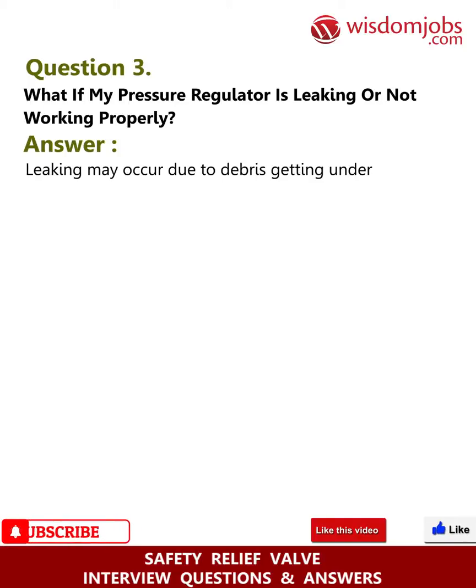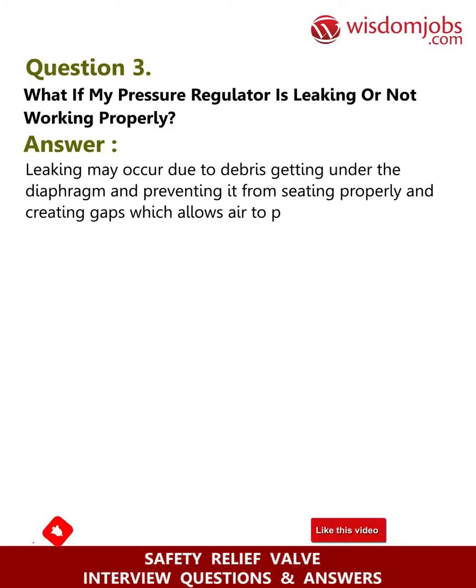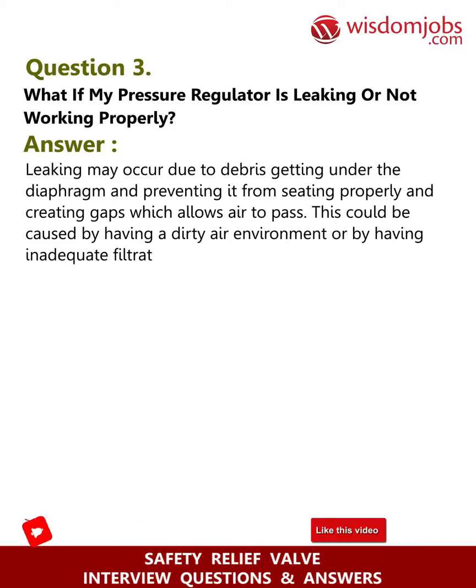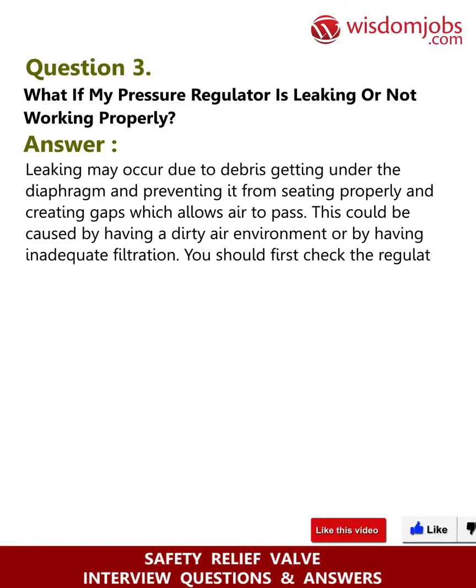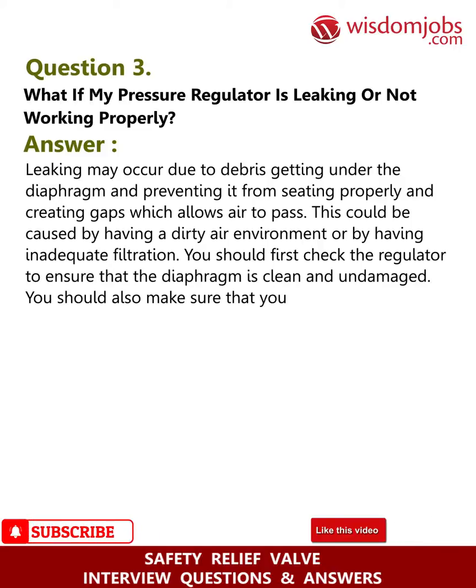Answer: Leaking may occur due to debris getting under the diaphragm and preventing it from seating properly, creating gaps which allow air to pass. This could be caused by having a dirty air environment or by having inadequate filtration. You should first check the regulator to ensure that the diaphragm is clean and undamaged.